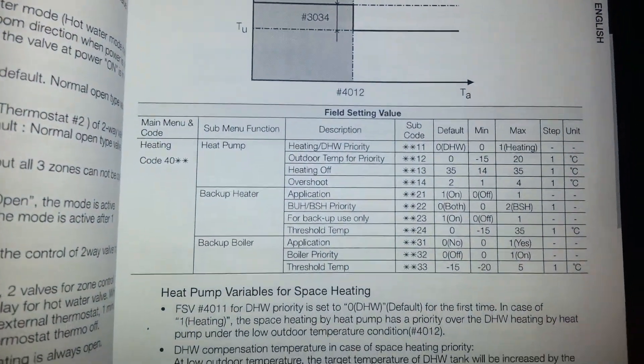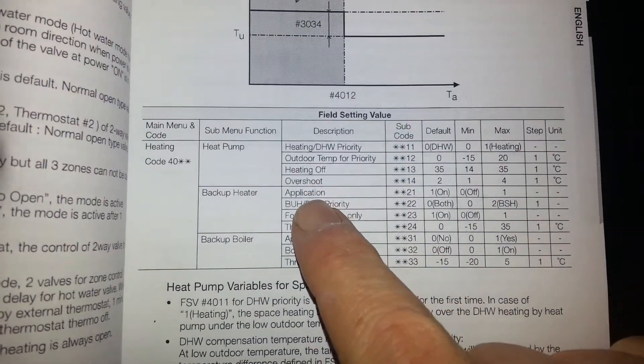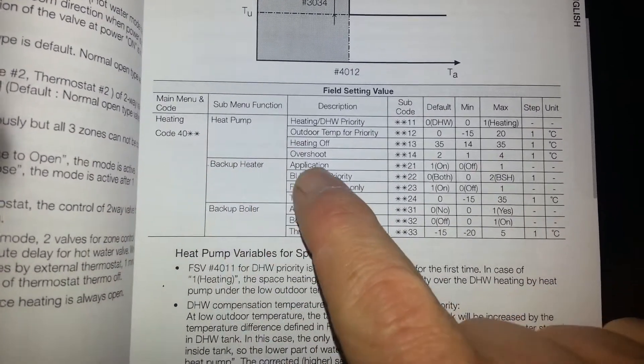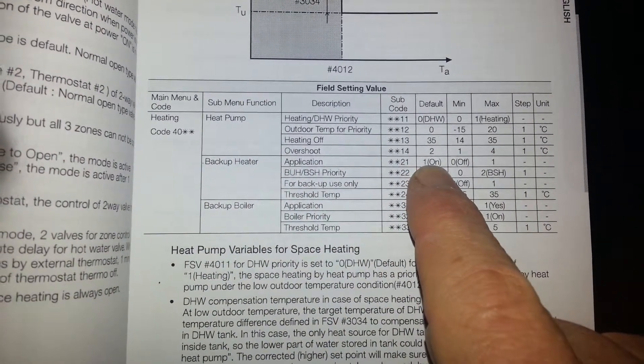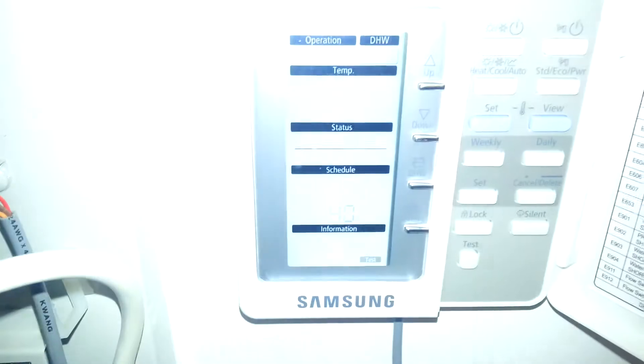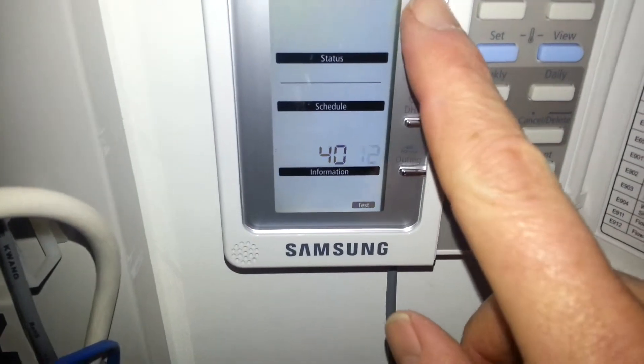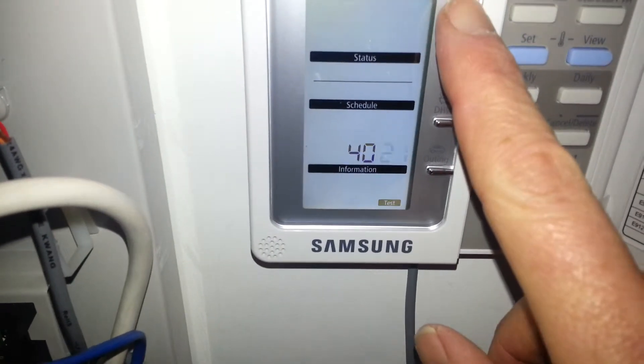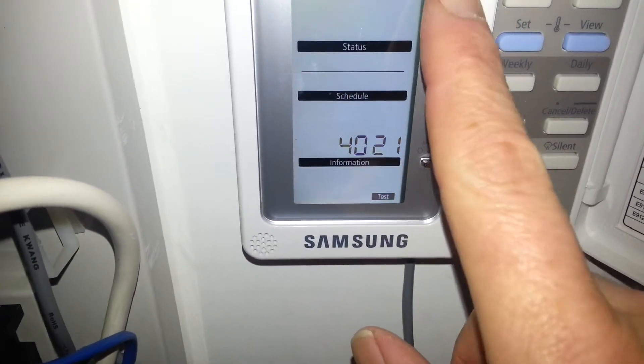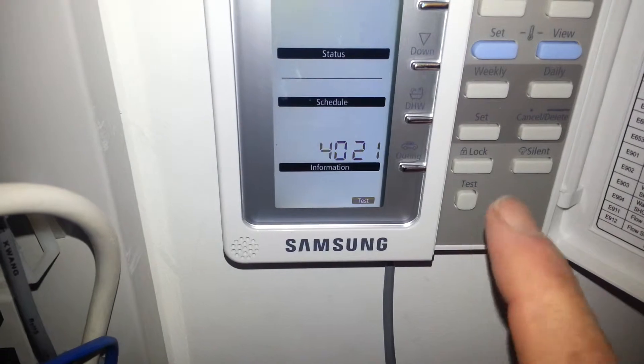I want to look at a problem that we get, which is E903 error. This is caused by telling the system that it has a backup heater in the field settings 40, 21, and setting it to number 1. If I go to my field settings and go up to 40, 21, and press set, and change it from the factory setting of 0 to number 1, which tells that a backup heater is installed.